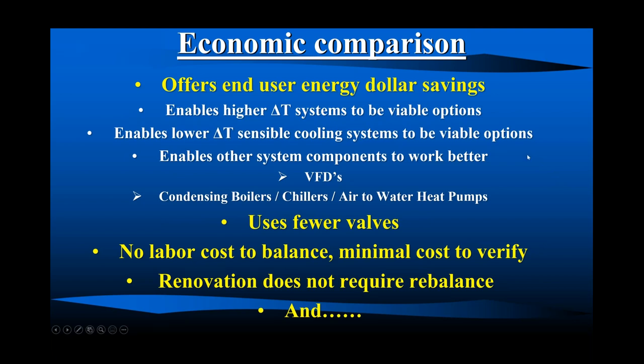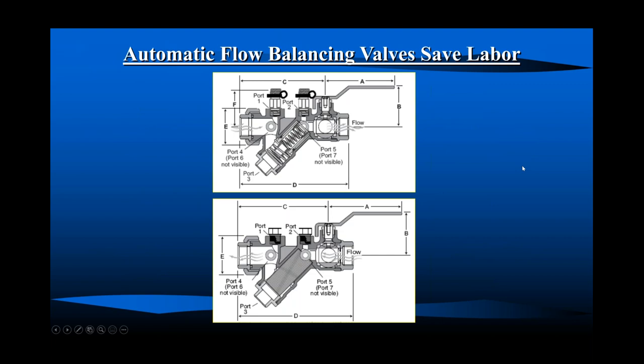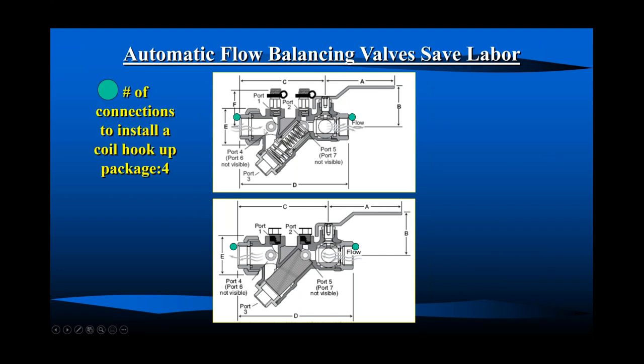And what else? Right? Save labor. All manufacturers of automatic flow balancing valves combine functions into one valve body. So one, two, three, four, right? This is a four hookup, four connection hookup. And there's our isolation valve, our strainer, our union. In its simplest form, this can go right on a terminal unit. There's our union and there's our return. There's our automatic flow balancing valve.